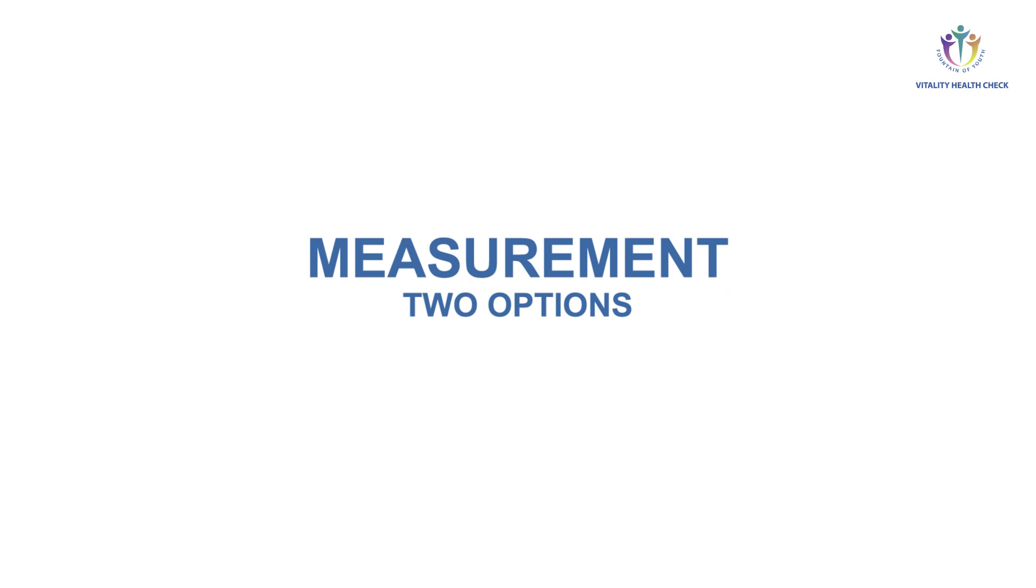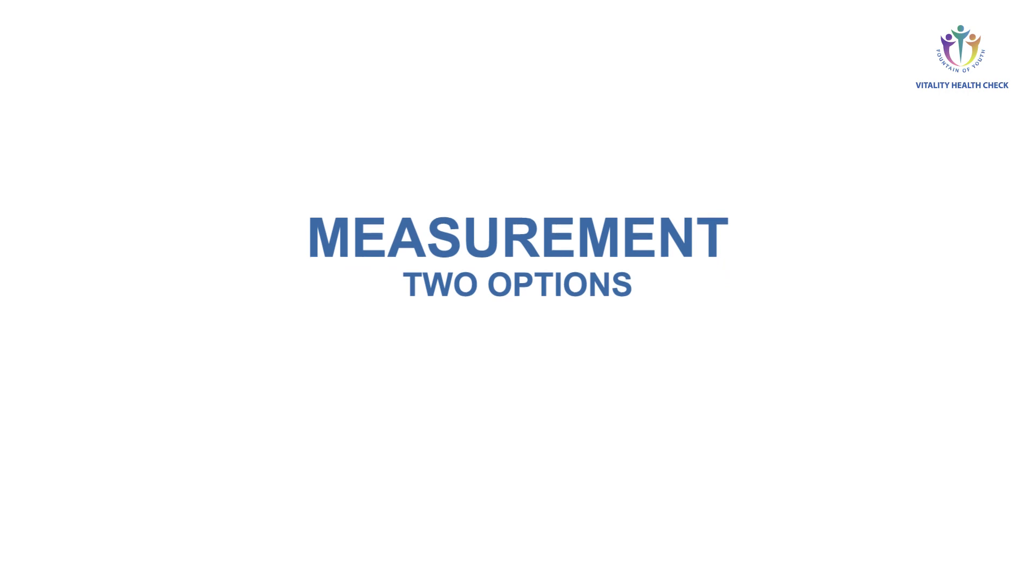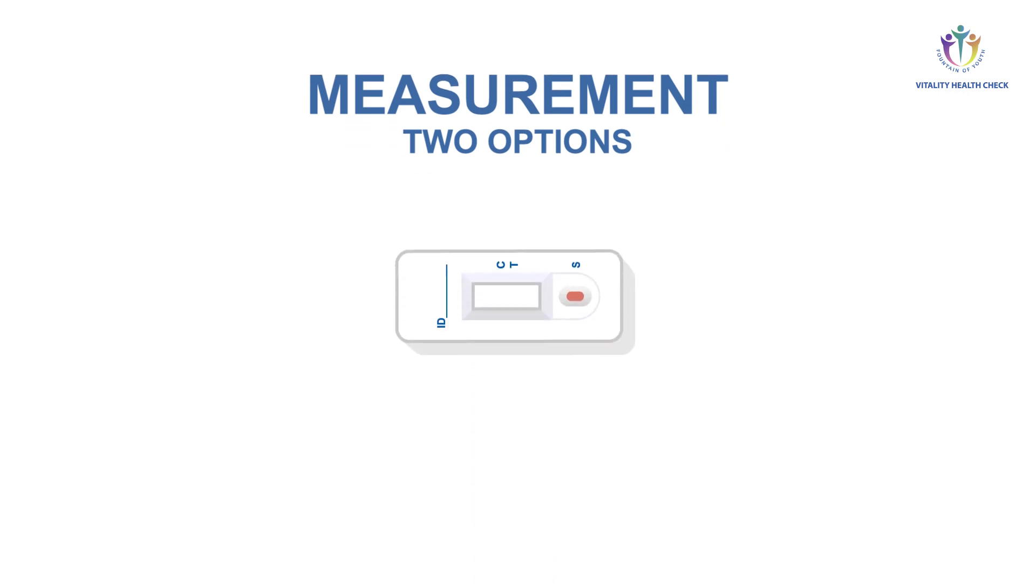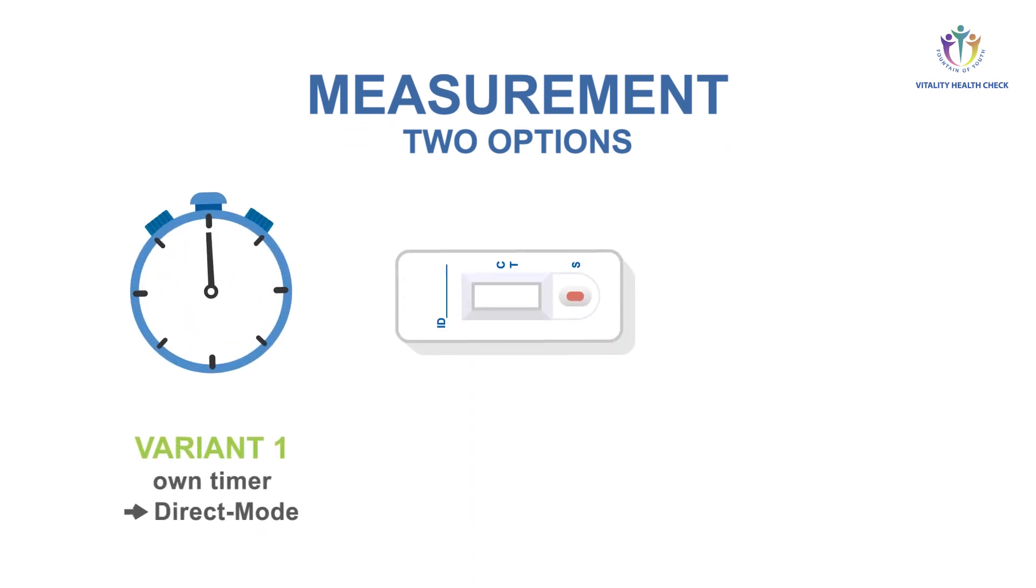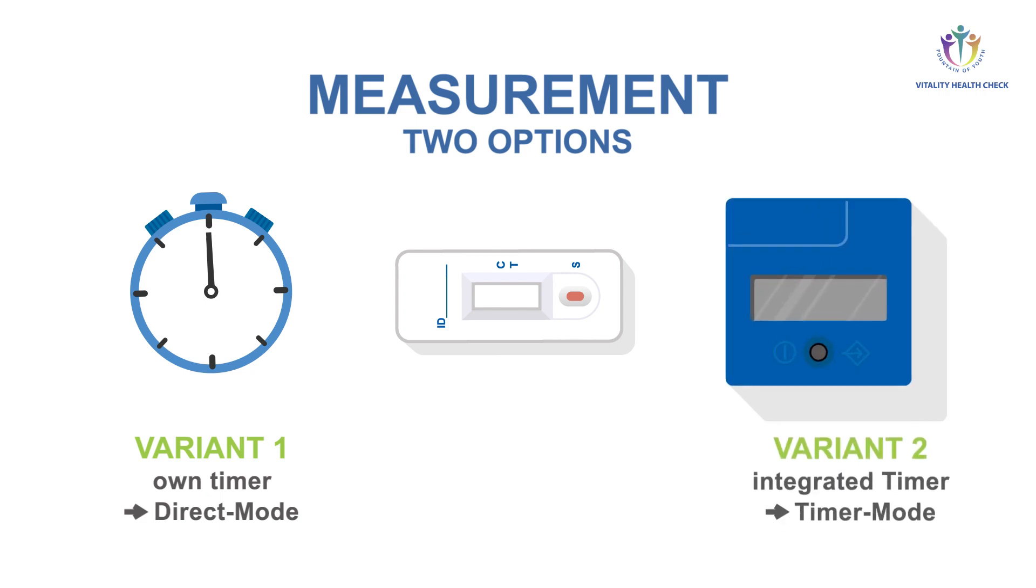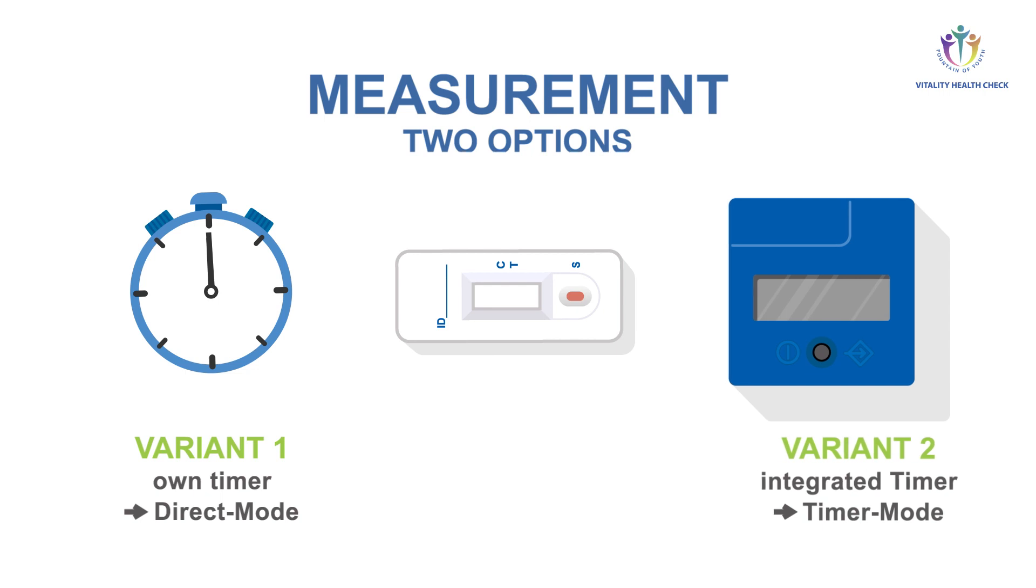There are two options to perform the measurement. 1. Measurement of the reaction time with your own timer and subsequent readout using the Direct mode of the VHC reader. 2. Use the timer mode of the VHC reader with automatic measurement at the end of the 15 minute reaction time.